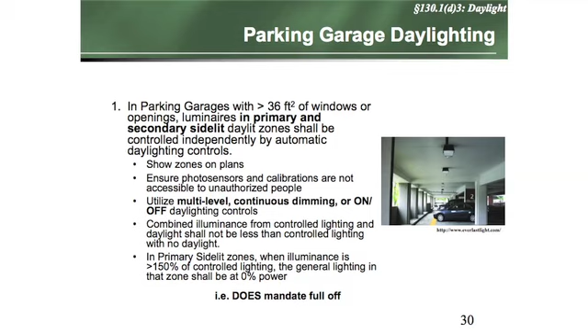In fact, what they say is that based on the levels that you've got to hit, if there is enough daylight, you have to turn the lights completely off. So garages used to be, you didn't have to do anything in there, right? Now you've got to do the high-low, which typically means you're going to have occupancy sensors to do that, and you've also got to have daylighting controls in the garages as well.